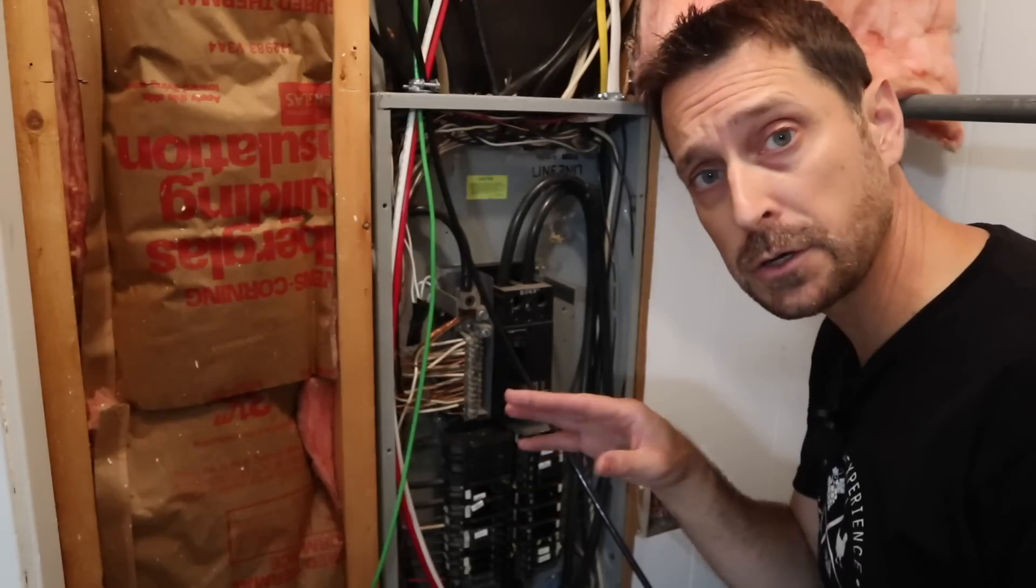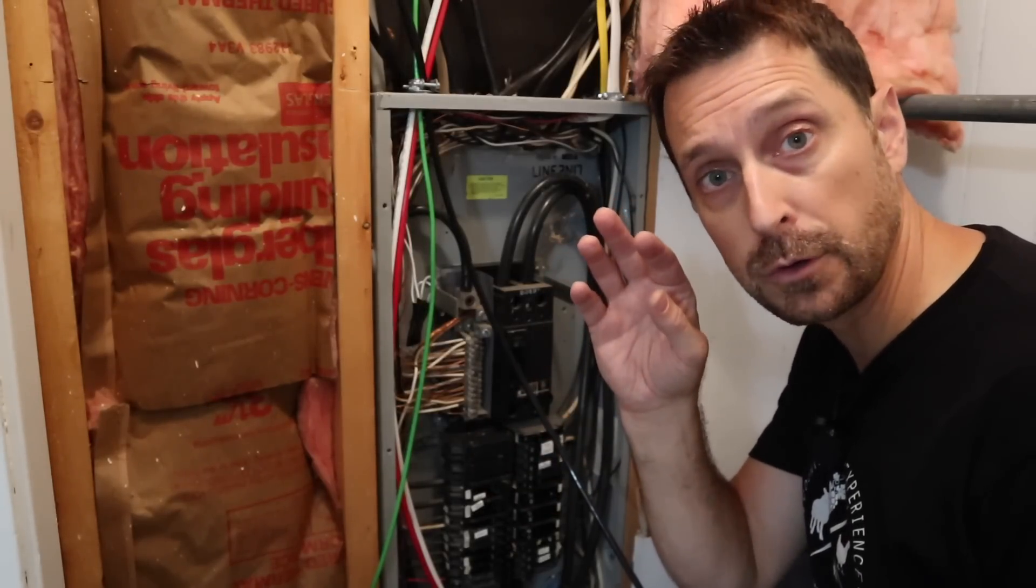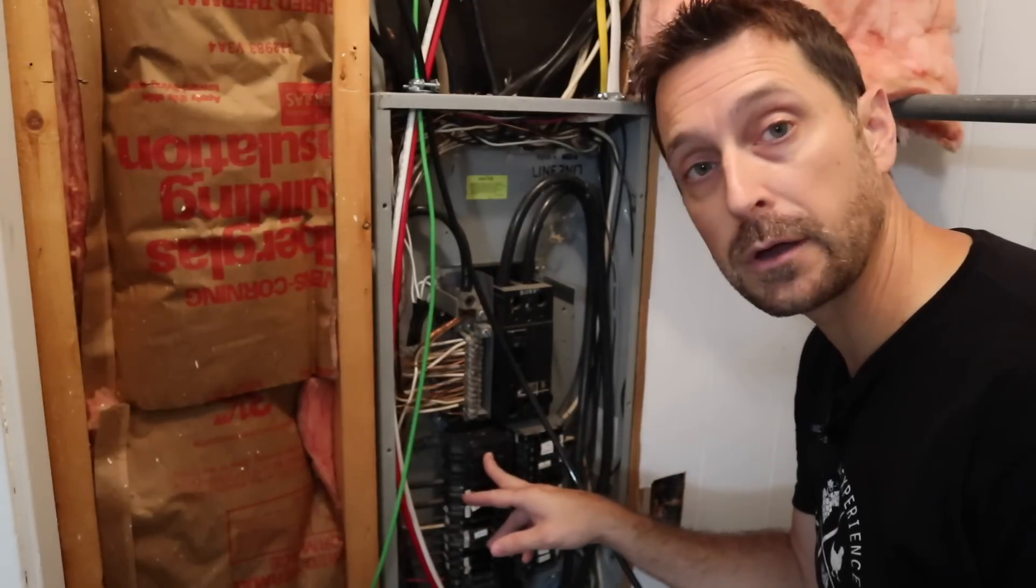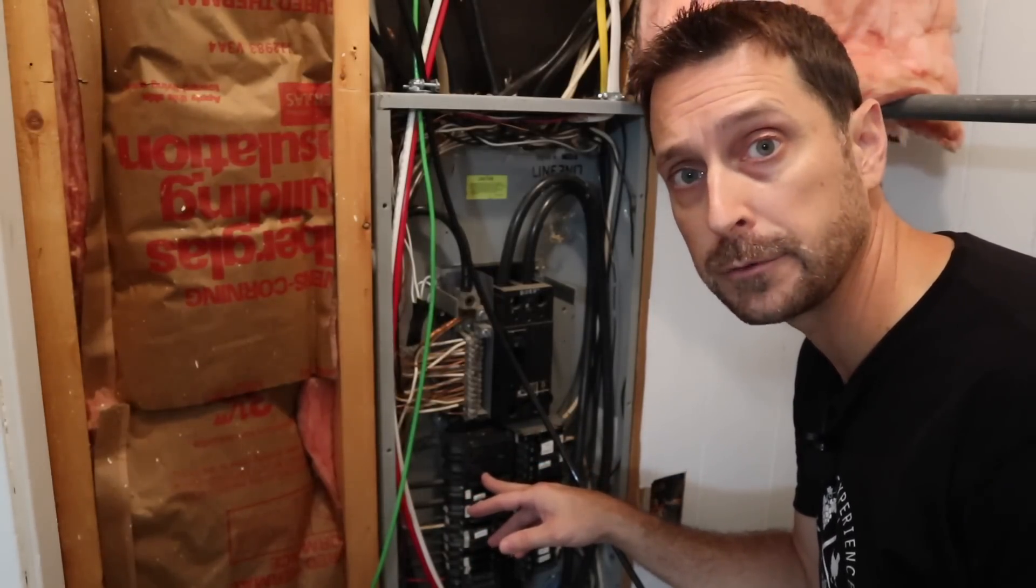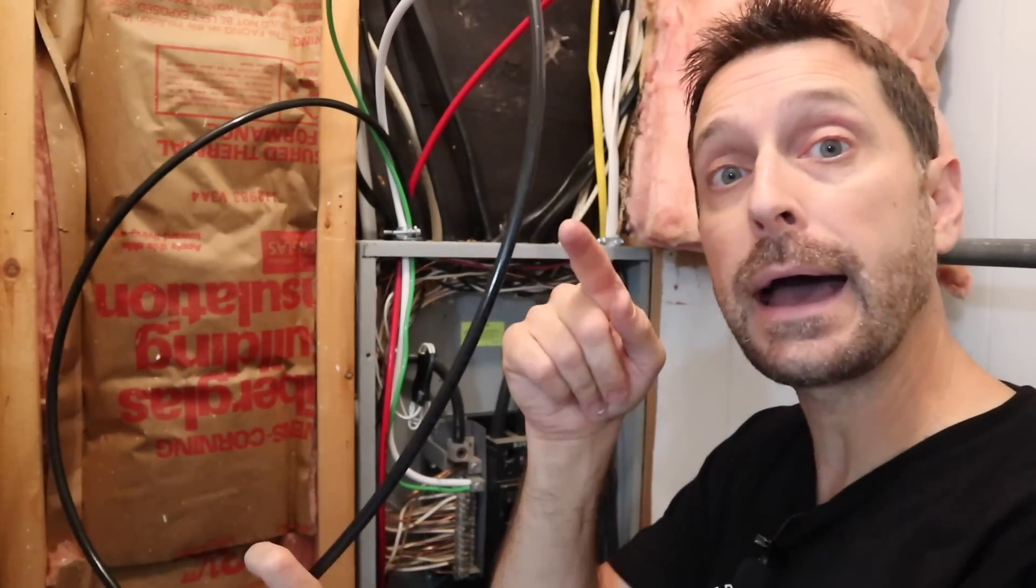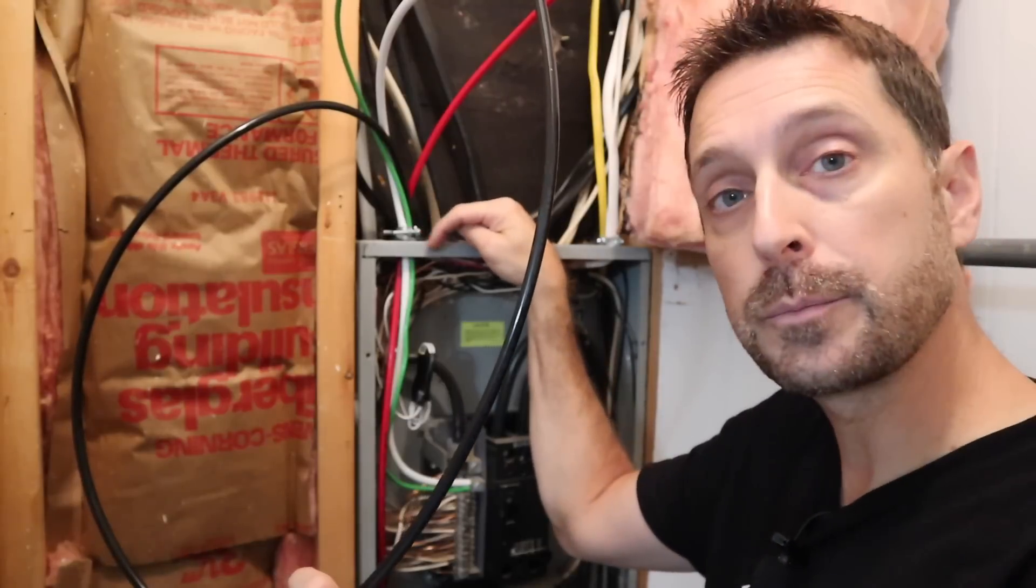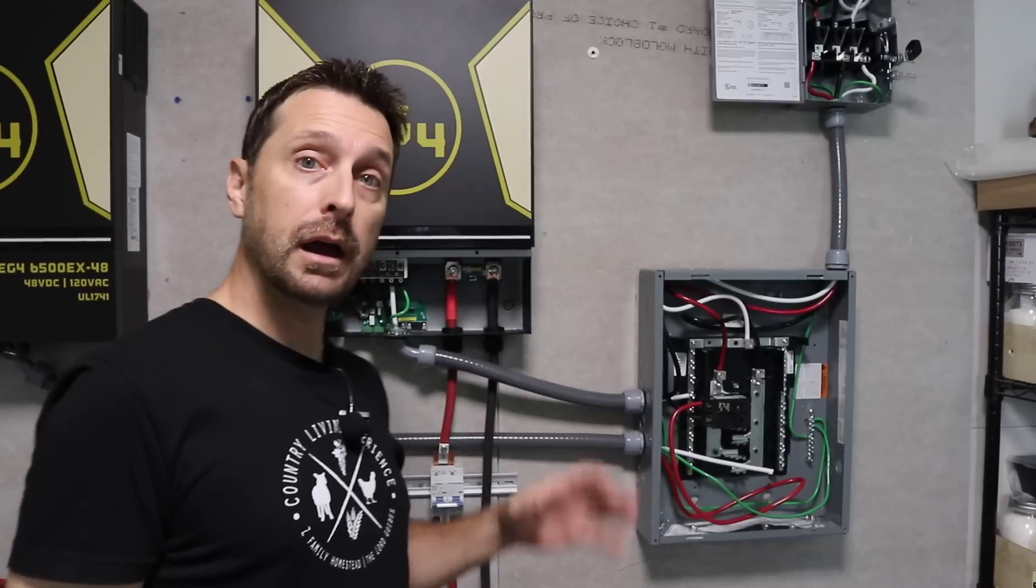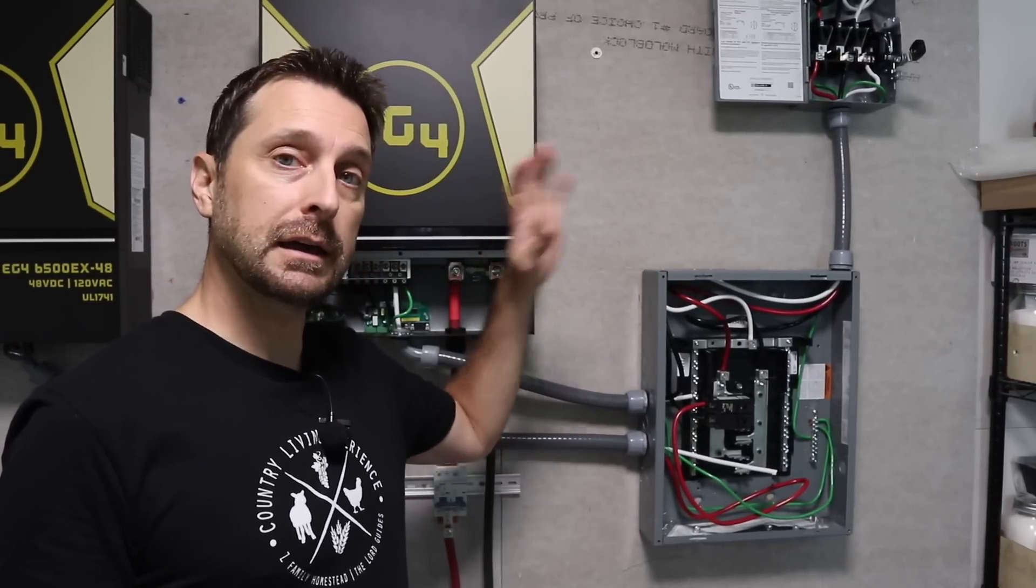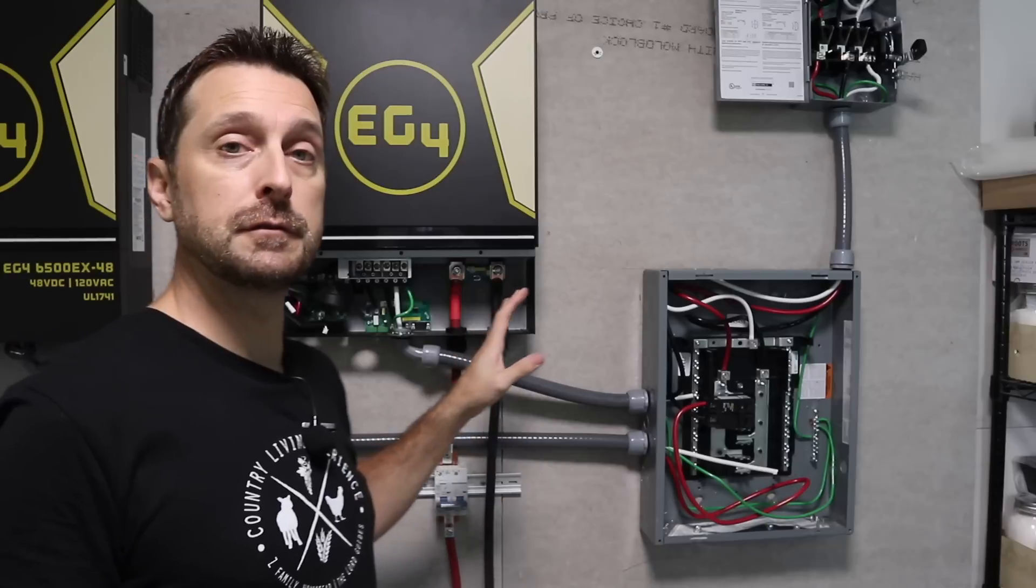Make sure when you're running through your whole system back from your other breaker through your safety switch and to this breaker that the L1 and L2 remain consistent or you're going to have problems. Everything's connected and we've got slack in the wire. I'm going to go back the other direction and pull it. I've got one of these knockout protectors here tightened down and that wire is not going to pull out.